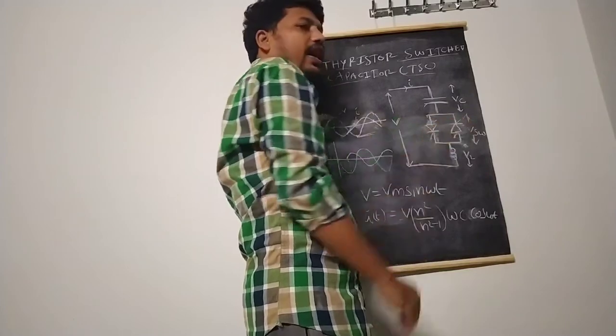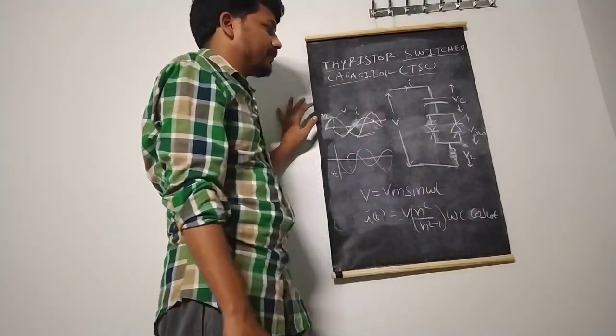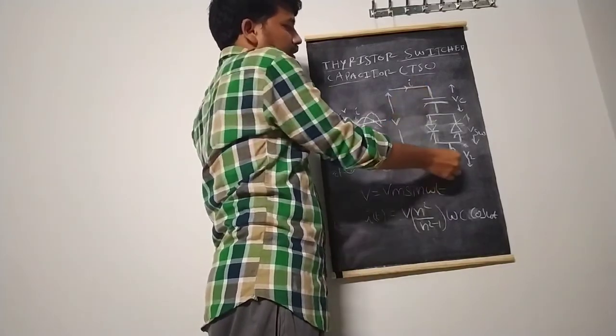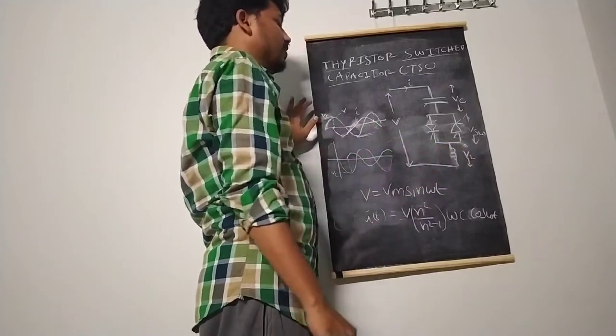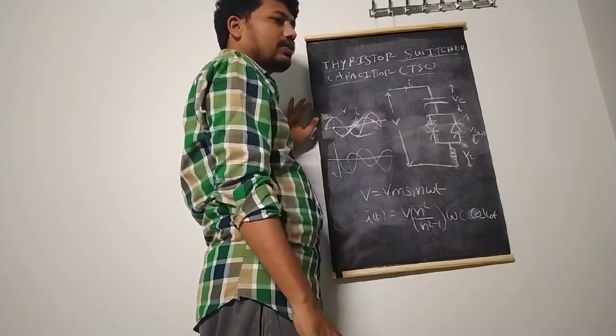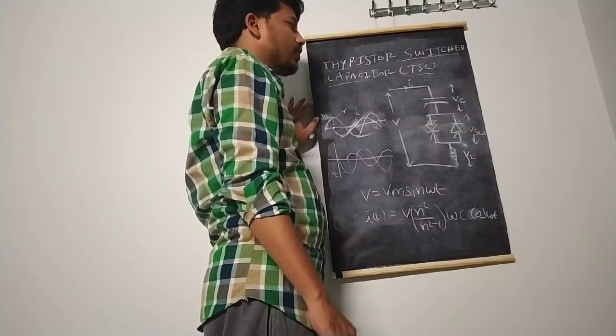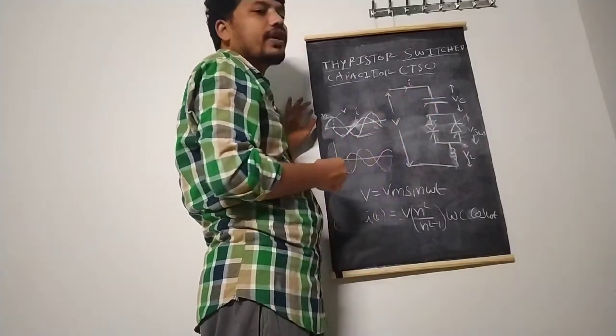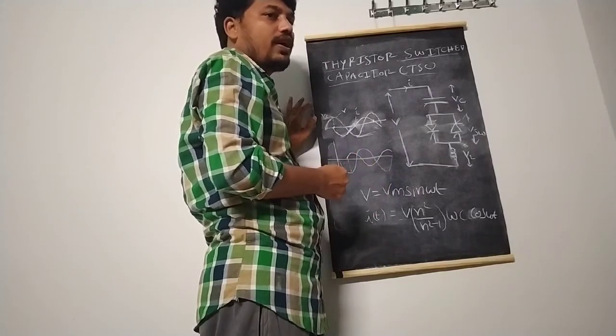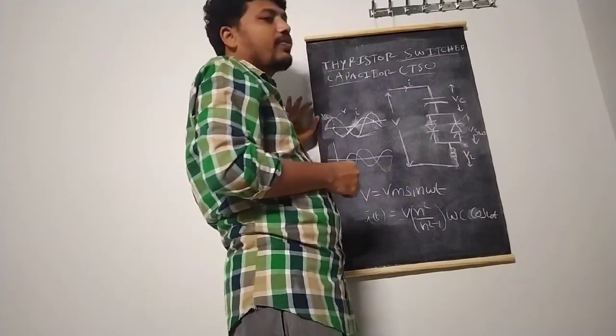During the turn-on condition, the switch voltage is 0 — whenever it is in on condition it is short, therefore 0. If it is in off condition, some voltage is present. With the help of this thyristor switch valve we can control the capacitance, that means the reactance of the capacitance. Therefore, with the help of this thyristor switch valve we can indirectly control the impedance — that is what is called variable impedance type. But since this is capacitor in nature and it is shunt connected, it is called variable admittance type.